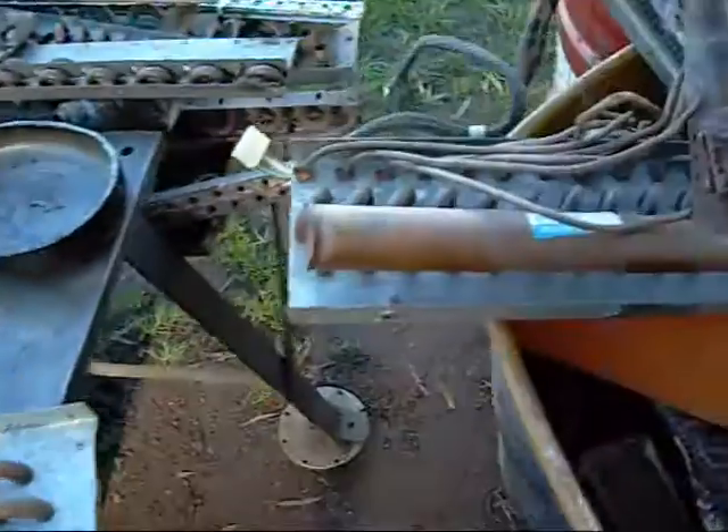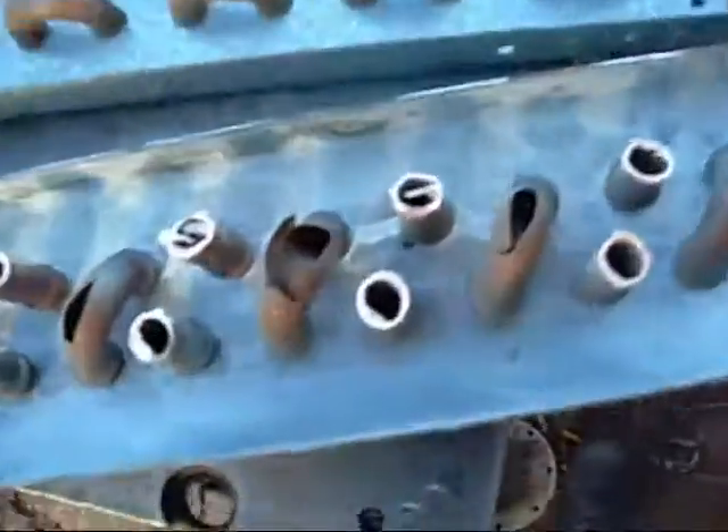Now that I look at this end plate over here, this one that ruptured could well be refrigeration. Because you've got one inlet along each of these tubes, one loop back through the coil, and one liquid out — which all accumulate into one liquid splitter, which is down there.